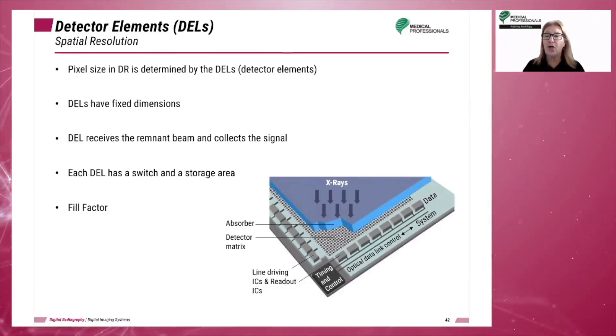Detector elements that are not sensitive to charge take up a certain amount of space. The fill factor refers to the sensing area compared to the non-sensing area. It is the percentage of the pixel or detector element face that is sensitive to x-rays. For example, if a detector has a fill factor of 80%, then the other 20% would be covered by the electronics. The fill factor has a direct relationship with both the spatial resolution and the contrast resolution. Detectors with a higher fill factor will provide higher spatial resolution and contrast resolution, according to Carlton and Adler.